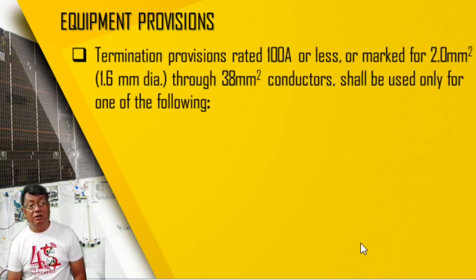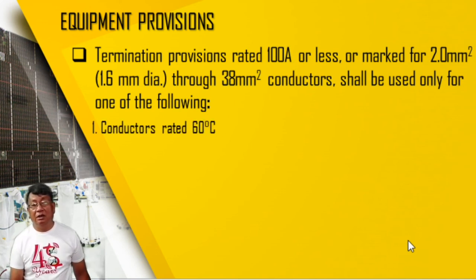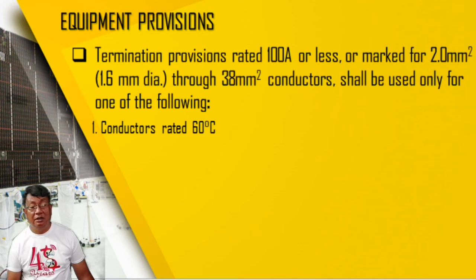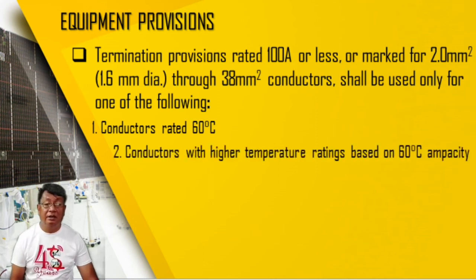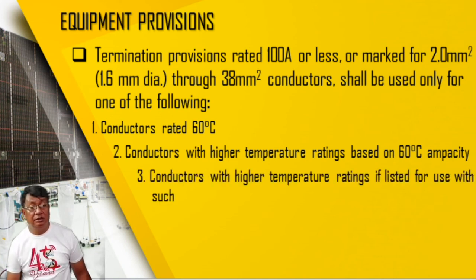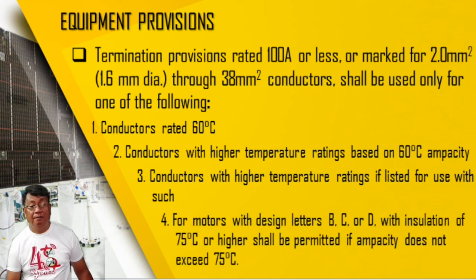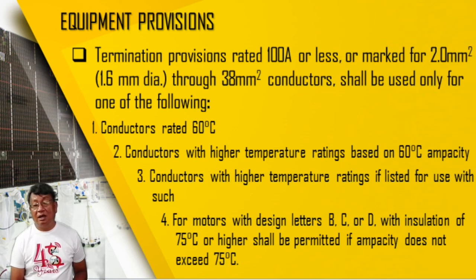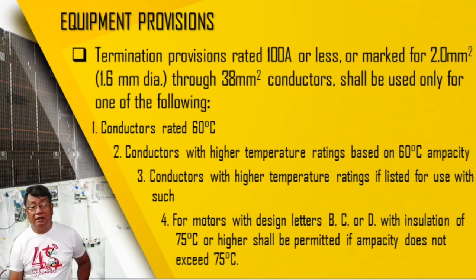Okay, so equipment provisions. Termination provisions rated 100 amperes or less, or marked for 2.0 to 38 millimeter squared conductors, shall be used only for the following. Conductors rated 60 degrees Celsius. Conductors with higher temperature ratings, provided the ampacity is based on 60 degrees Celsius. Conductors with higher temperature ratings, if listed for use with such. Okay. For motors with design letters B, C, or D stamped on the nameplate of the motor, conductors with insulation rated 75 degrees Celsius or higher shall be permitted if the ampacity does not exceed the 75 degrees Celsius ampacity.